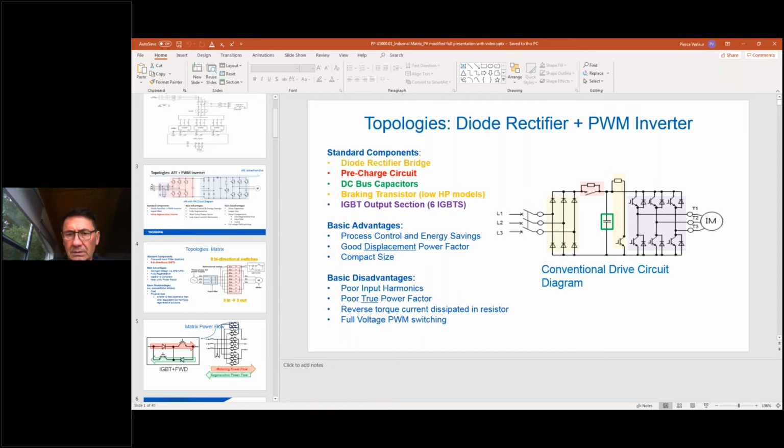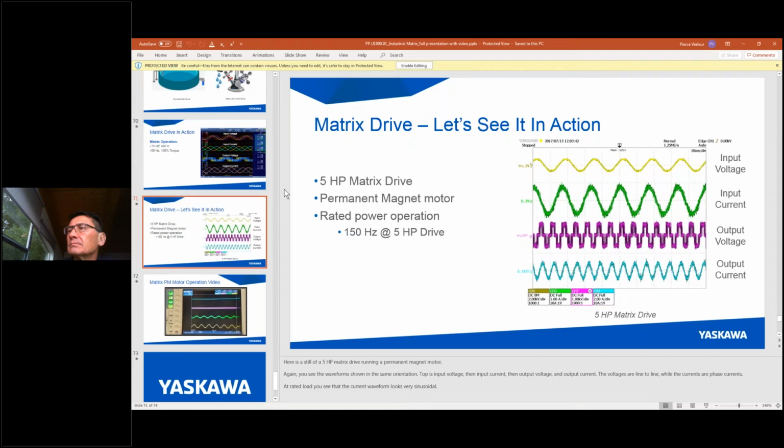Okay, on the thermal stresses on the motor with the harmonics, especially on submersibles, we've discovered that different harmonics cause the motor to react differently. Basically, it puts the motor into either a forward state, a no torque state, or literally a reversing state, all happening while the sine wave is being created and the harmonics are reacting with the motor. So all this causes the motor to heat up. And then we throw on top of it a couple hundred feet of water column, and it causes the motor to do what we call a torque ripple.